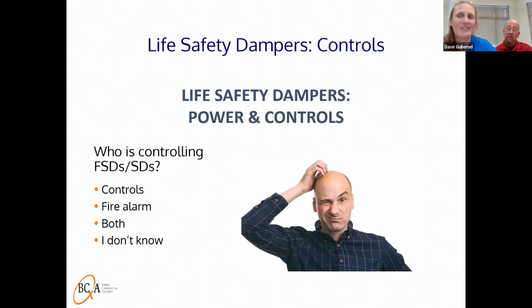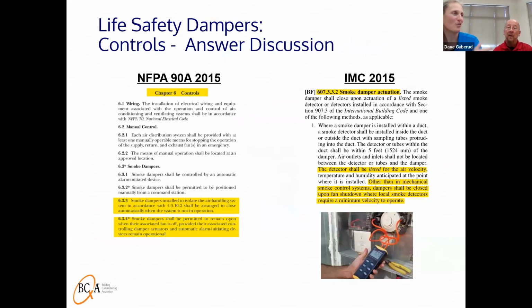So we talk about these things at the very beginning of the project now, because it is not always defined as it should be. So having a real understanding of who's controlling the smoke dampers, especially because they have to be controlled for fire alarm reasons, and they have to be controlled for control reasons. Anytime your air handler system is down, your dampers must be closed per these two code requirements.